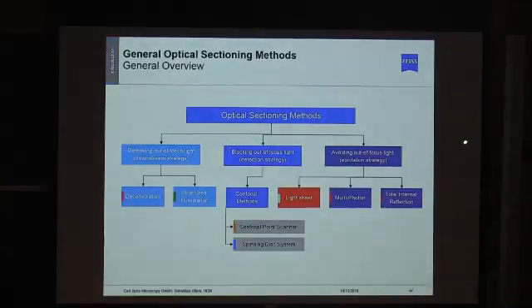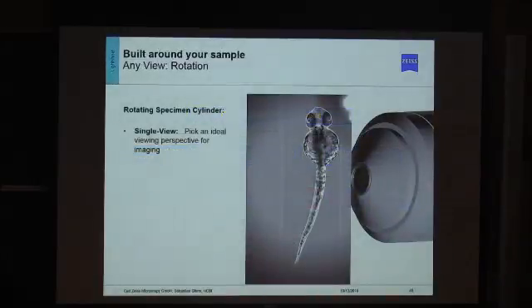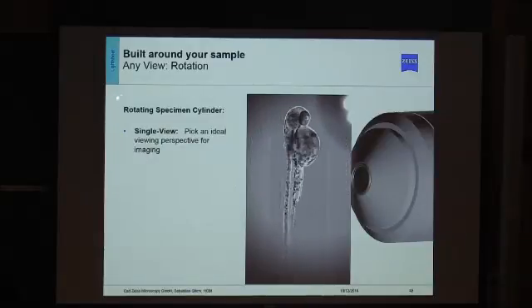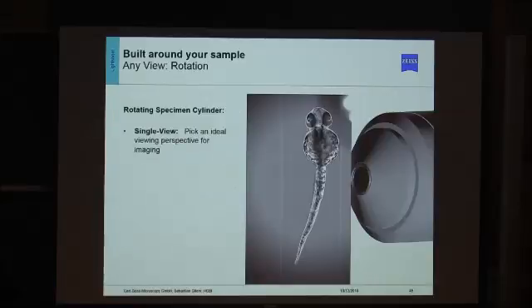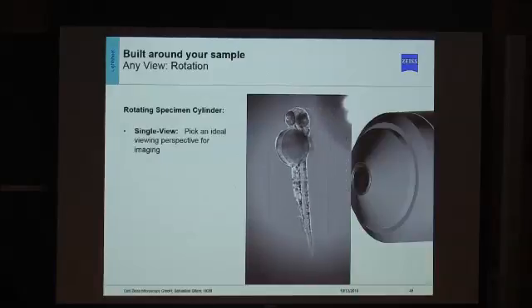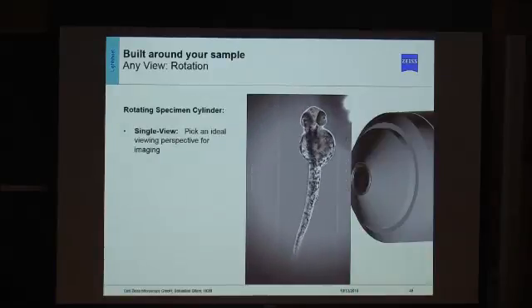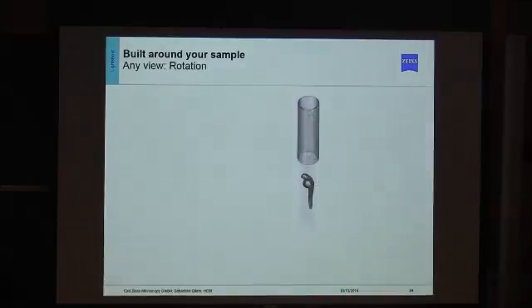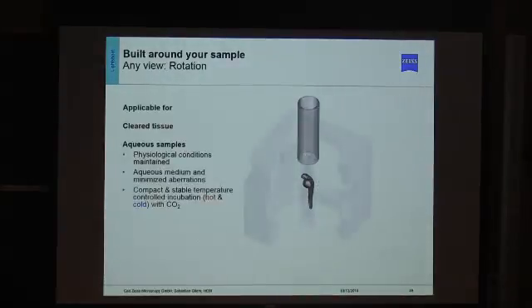Now let's move to the excitation strategy branch of the optical sectioning family. I'd like to start with the light sheet system. One of its great advantages is that the system is built around the sample — you can take a specimen cylinder or syringe and orient it in any way you need for imaging. In case you need to rotate your sample, the light sheet system is the system you should use. You can also apply certain physiological conditions like accurate temperature control and CO2 concentrations.